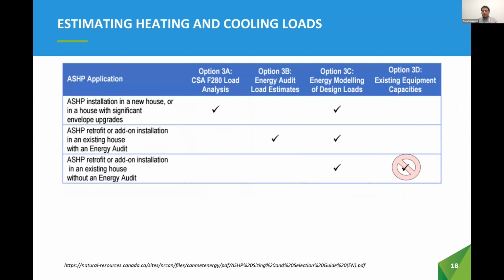In the NRCan heat pump sizing guide, they suggest several methods of estimating heating and cooling loads, which are shown here, aligned with several different air source heat pump applications. CSA F280 load analysis can be used for new construction as well as for existing houses which have undergone extensive envelope upgrades to improve their energy efficiency.